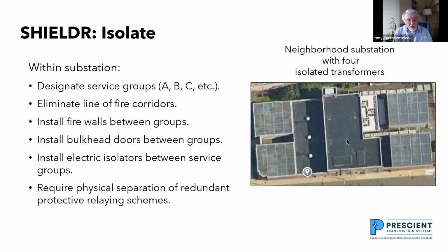They've put firewalls between groups, and they've put bulkhead doors between groups. And they're putting electric isolators between service groups. Electric isolators in my world is circuit breakers. But I use the term electric isolators to drive home the point that a circuit breaker is an isolation device. And they required physical separation of the redundant protective relaying scheme. So some utilities are doing this. A lot of utilities are not.